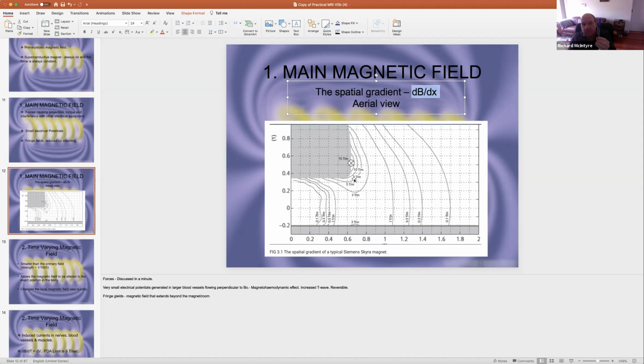Okay, so if I was to take this ferromagnetic object into the room, it would have a small pull over here. Not just because the magnetic field is less, so it might be 0.5 of a Tesla over here, but because the change in magnetic field is less over here. It's only 0.1 Tesla per meter, which is a small change. It might be enough, well, it probably would be enough to really feel a strong pull of this magnetic field.